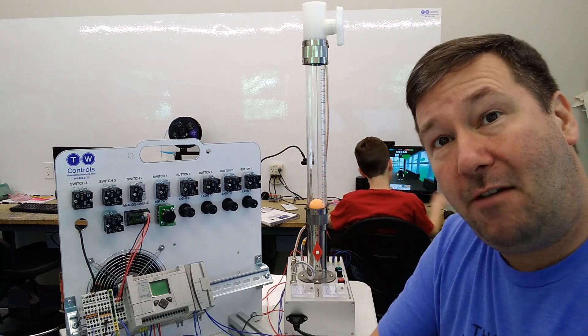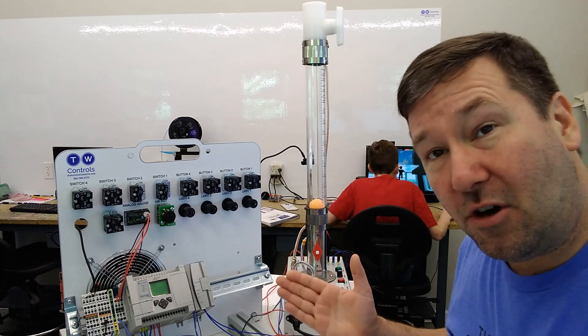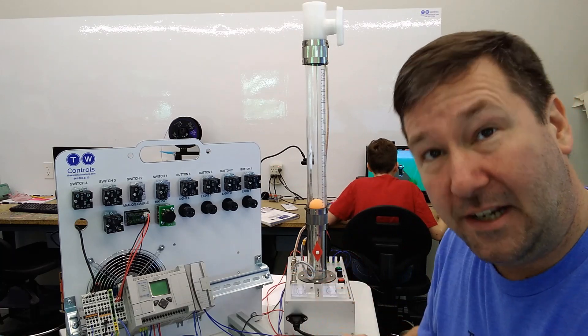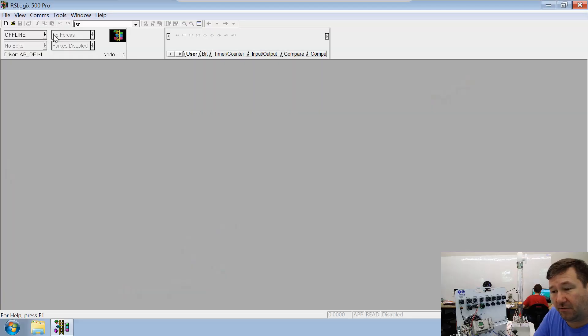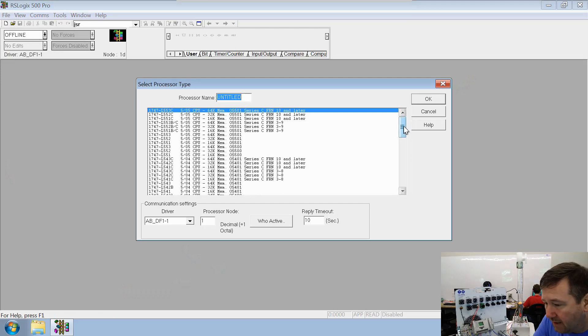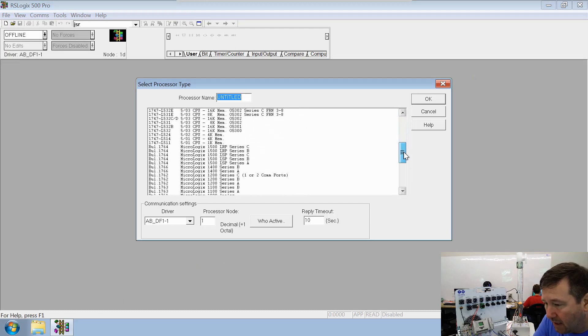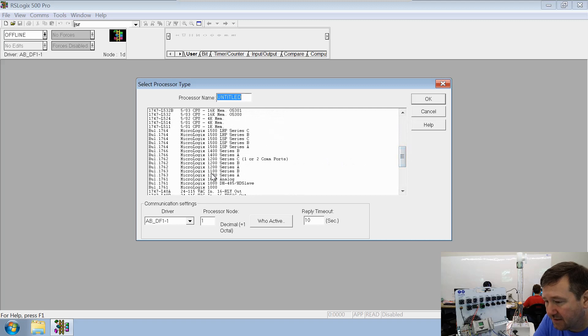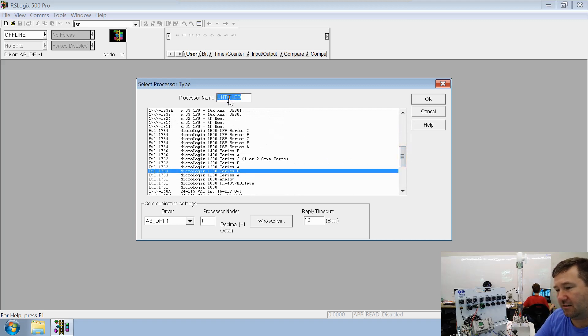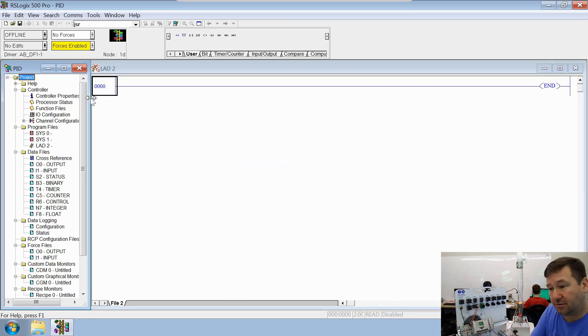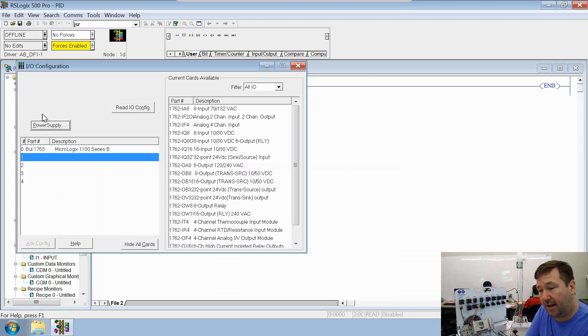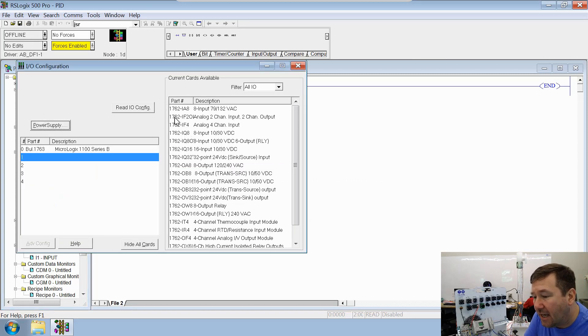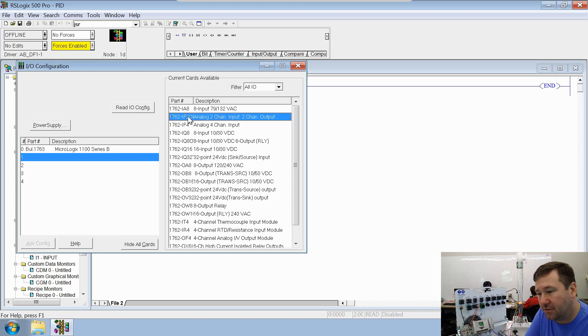And now we're going to create a basic program just to make sure all of our wiring is working. So we're going to start with a new program, in RS Logix 500, and we have a 1763 MicroLogix 1100 PLC, and it's a series B, and we're just going to call this processor PID. And then we need to add our analog modules to our I.O. configuration. So we're going to open up our I.O. configuration, and on the right side, let's find that 1762 IF2 OF2.